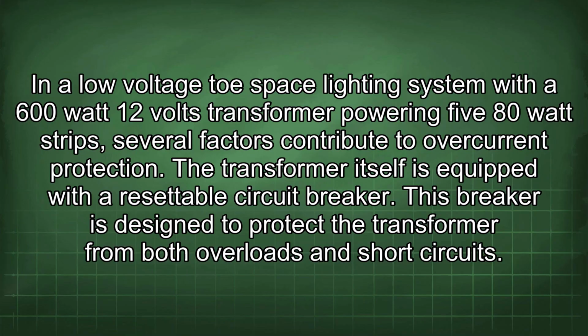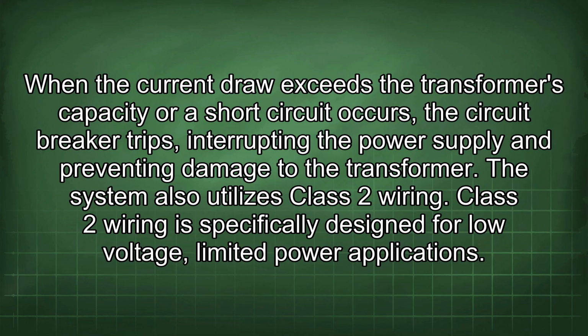In a low-voltage toe-space lighting system with a 600-watt 12-volt transformer powering five 80-watt strips, several factors contribute to overcurrent protection. The transformer itself is equipped with a resettable circuit breaker. This breaker is designed to protect the transformer from both overloads and short circuits. When the current draw exceeds the transformer's capacity or a short circuit occurs, the circuit breaker trips, interrupting the power supply and preventing damage to the transformer.